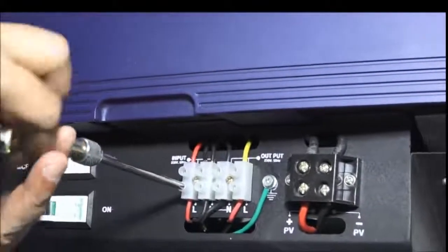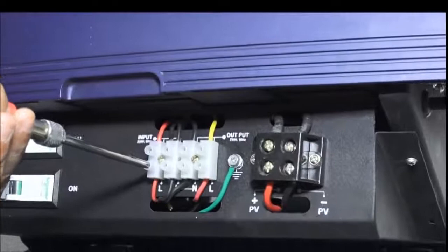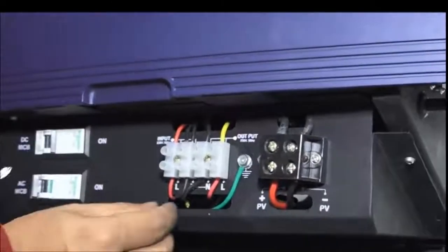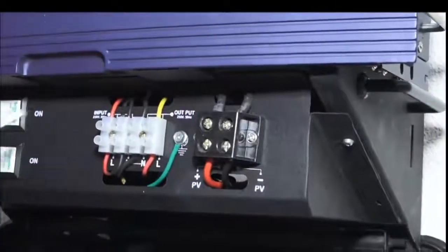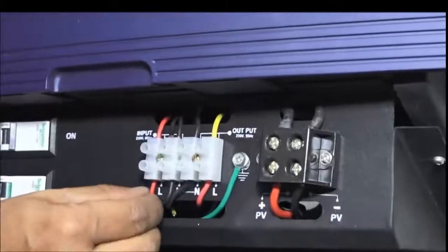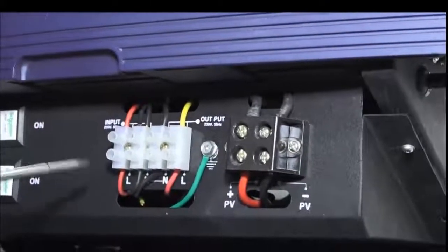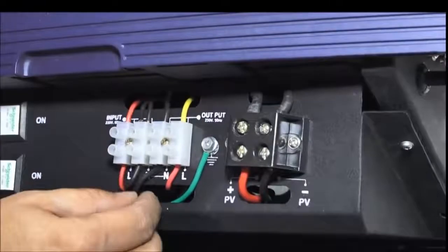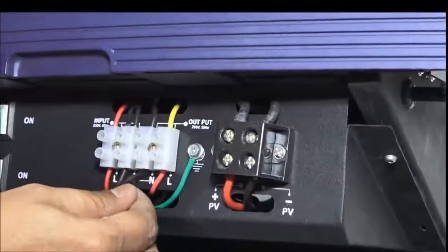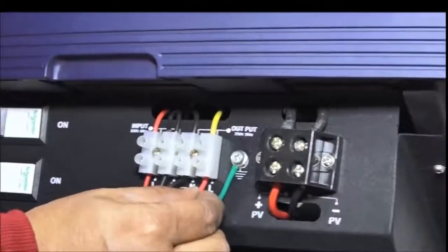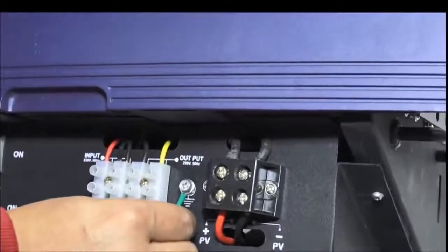Pass all wires through the hole in the back of the inverter and bring it to the front on the bottom panel. In the bottom panel, we have the terminal block. From the left, the connectors are mains live, mains neutral, output neutral, and output live. The earth wire is on the right, which is mandatory.